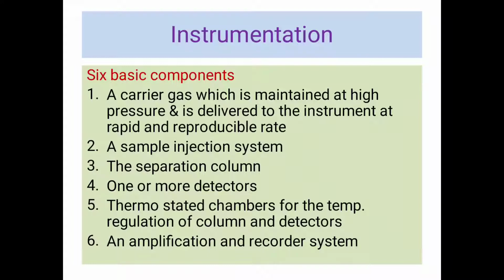Then instrumentation: there are six basic components. First is the carrier gas, which is maintained at high pressure and delivered to the instrument at a rapid and reproducible rate. Then a sample injection system, then the separation columns and one or more detectors, then thermostated chambers for temperature regulation of the column and detectors, and the last one is the amplification and recorder system.